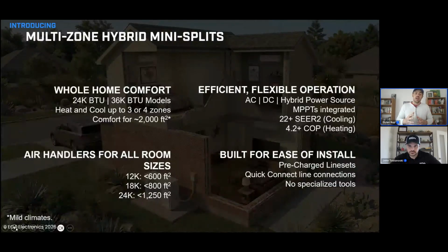However, I always do recommend that you perform a true heat load calculation when sizing those air handlers for the best results. And we'll talk a little bit more about that at the end of the presentation here, but especially if you're in a unique application case, a heat load calculation is going to be the best means of sizing those air handlers. So this does give you some nice back of the envelope guidance here.